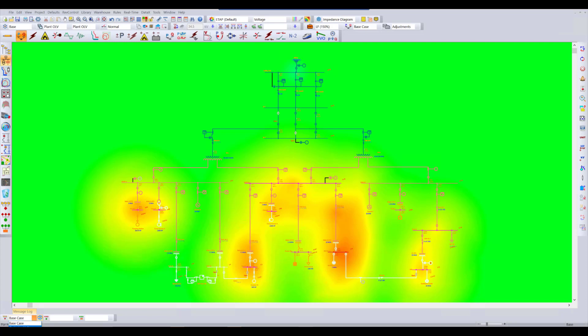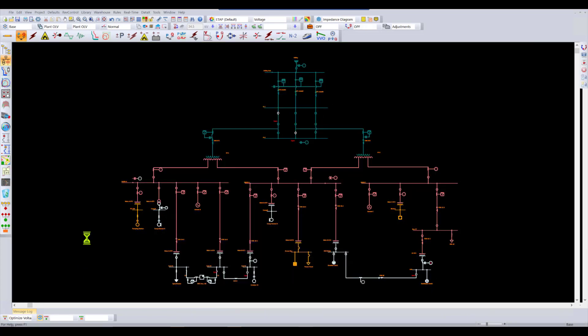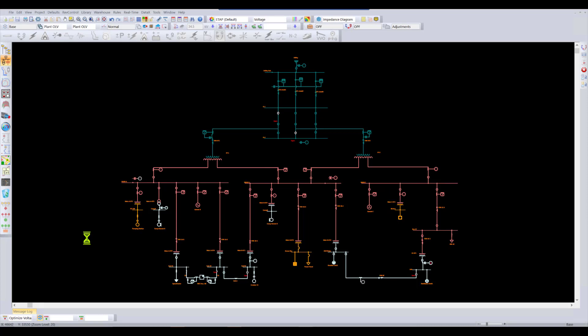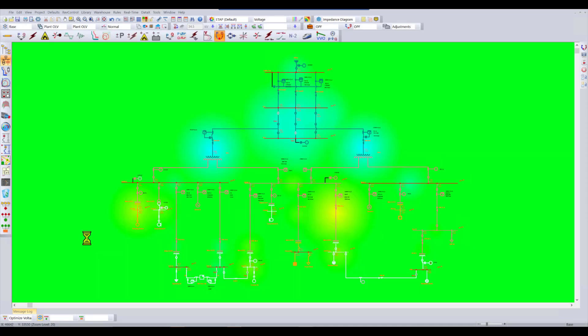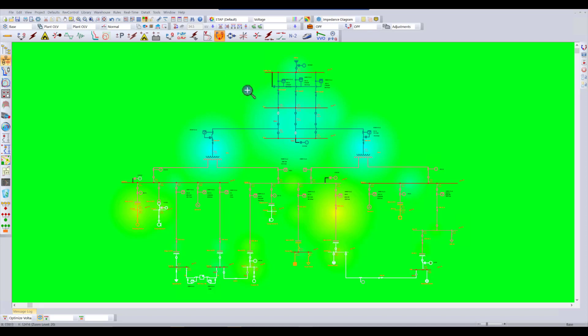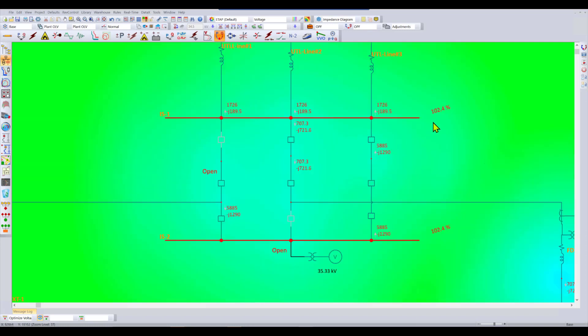I've already set up OPF to flatten the voltage profile, so we can see what happens when OPF runs. Those orange red areas have essentially been eliminated and replaced with slightly bluer areas, which means we are slightly over the nominal values. We can zoom in and see how much over we are, at about 102 percent or so of the nominal values. This is basically OPF trying to use the various controls that we have in our system to get to these healthier voltage levels.